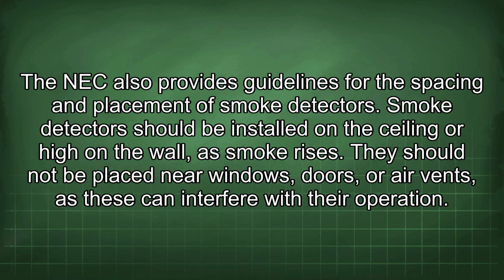The NEC also provides guidelines for the spacing and placement of smoke detectors. Smoke detectors should be installed on the ceiling or high on the wall as smoke rises. They should not be placed near windows, doors, or air vents, as these can interfere with their operation.